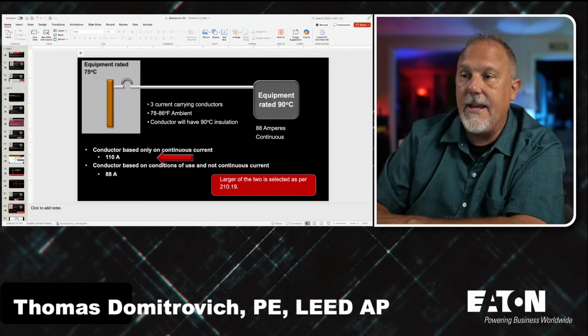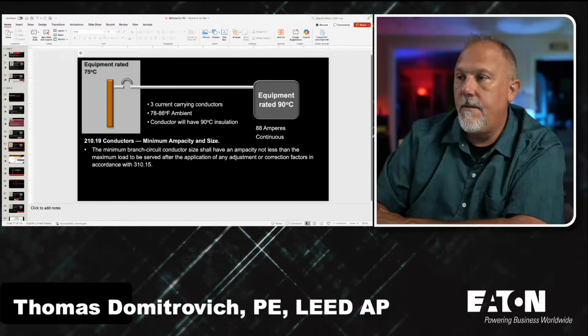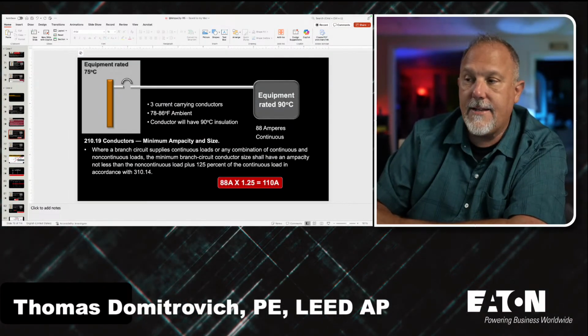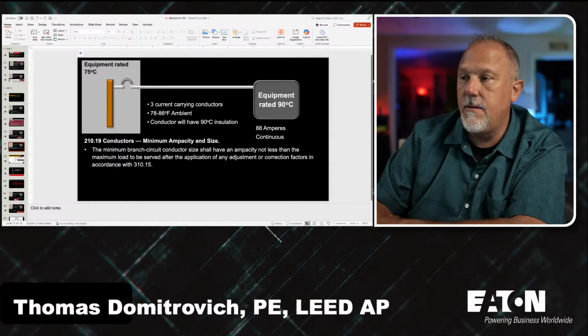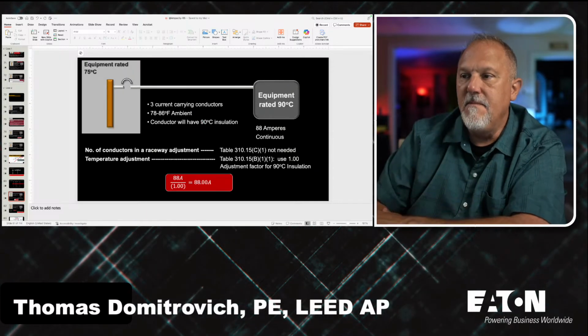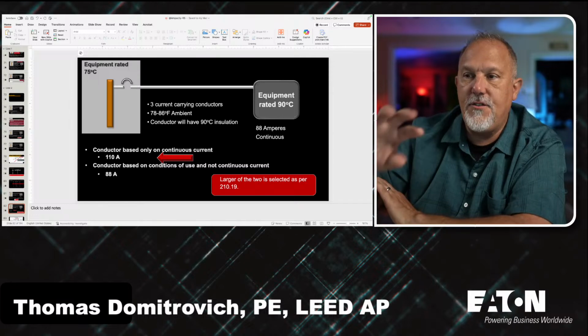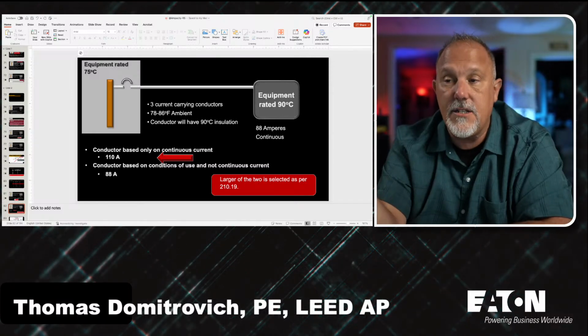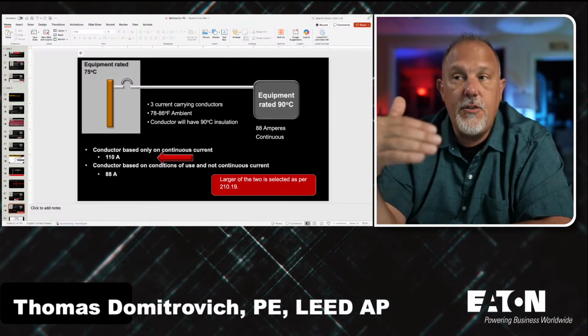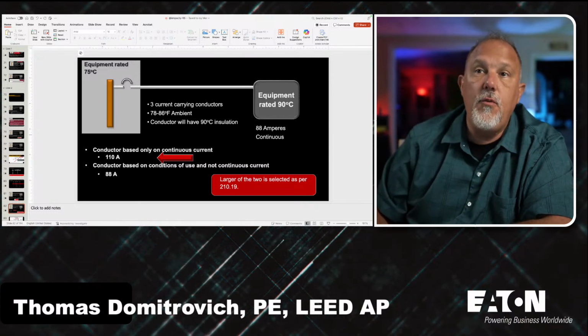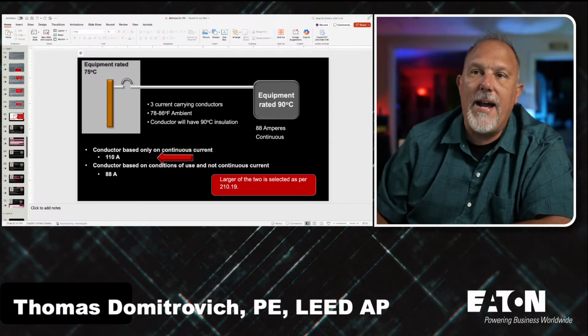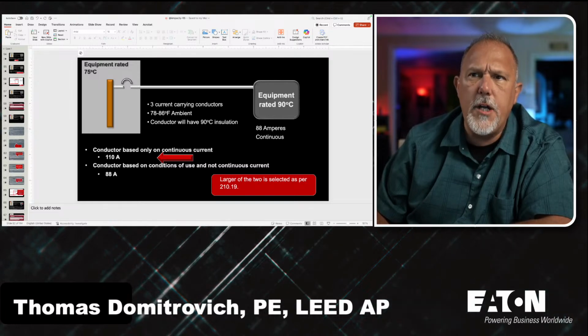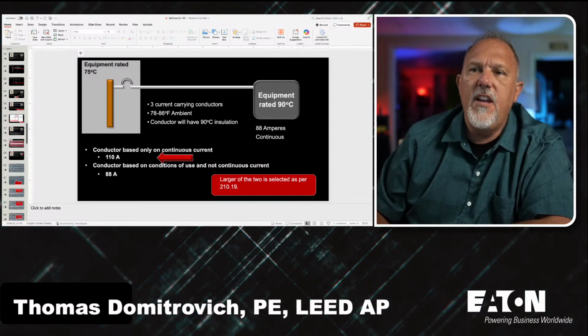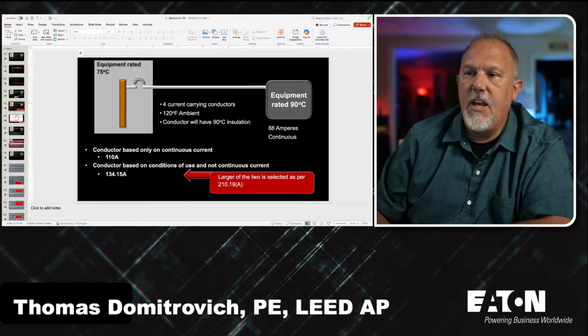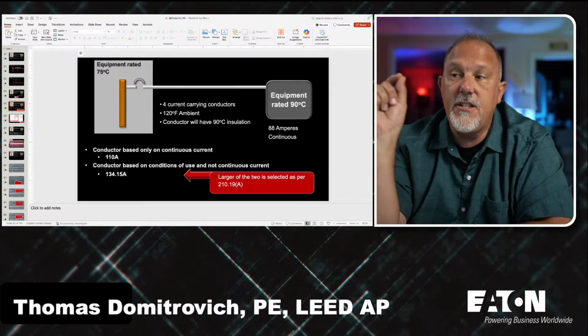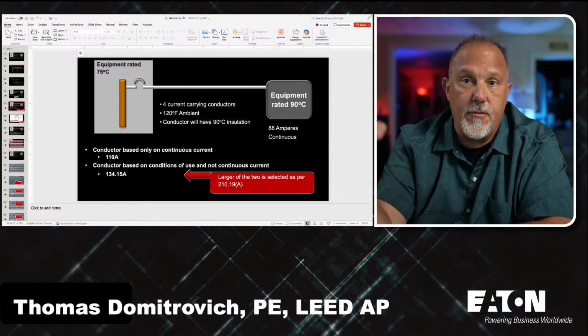So I begin, let me go back to here. 88 times 1.25 was 110 amps. Here, 88 amps. I do the calculation, and in this case my continuous current was the larger of the two. If you recall, let's go back. If we go back, it was the opposite. The conditions of use gave me a larger number.